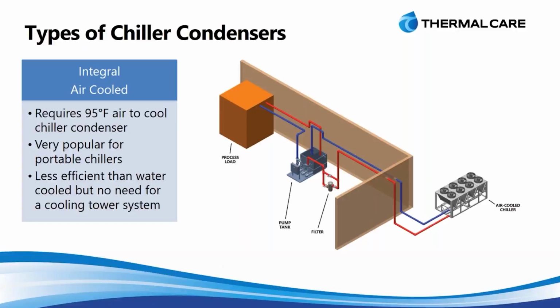The first being an integral air-cooled, which would be kind of like a packaged unit. And so what we've shown here is an outdoor air-cooled unit with a separate pump and tank system. That pump and tank system could actually still be incorporated into the chiller itself, but here it does a good job of illustrating how the components work together. With that outdoor air-cooled unit, the integral air-cooled unit, we have those fans that are depicted there. And what those fans are actually doing is they're forcing air over an air to refrigerant heat exchanger. And so as that air is forced across there, it pulls the energy out of the refrigerant and allows that refrigerant to then cycle back through its refrigeration cycle to cool the process water.